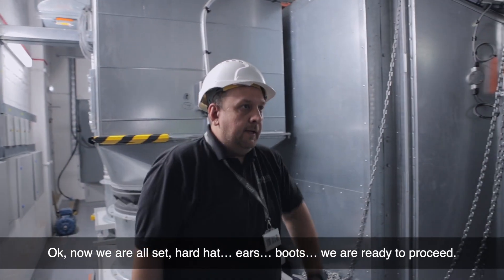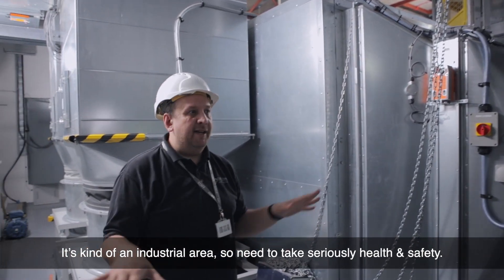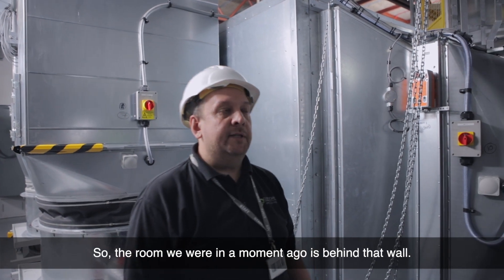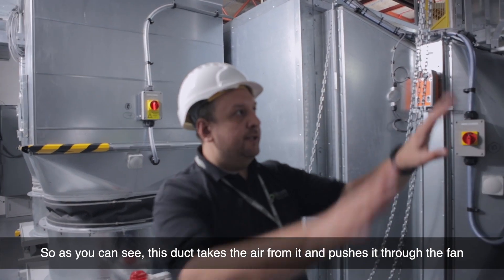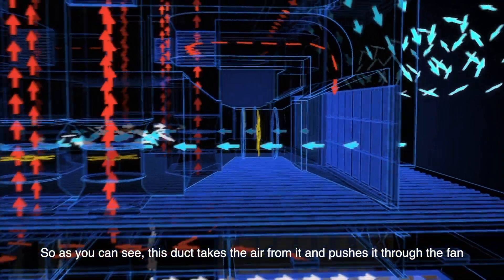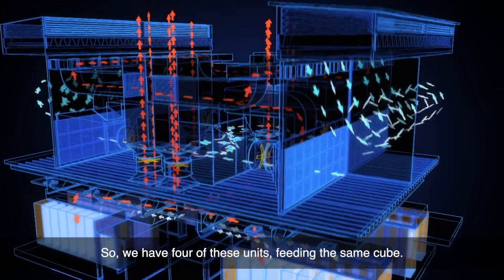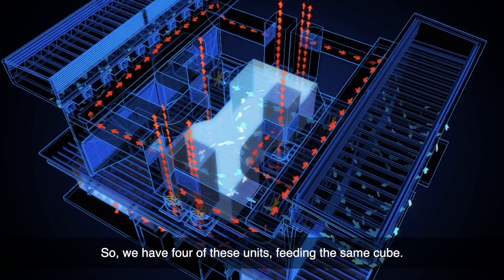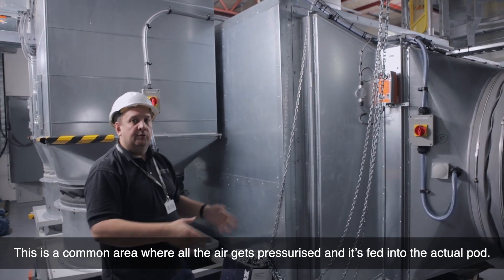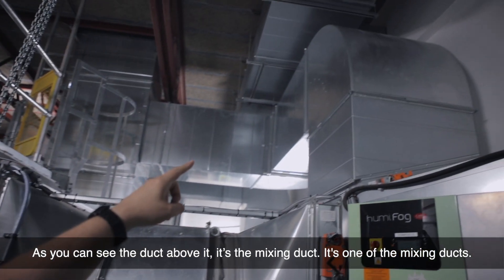Now we're all set — hard hat, ears, boots. We're ready to proceed because it's a kind of industrial area, so we need to take serious considerations. The room we were in a moment ago is behind that wall. This duct takes the air from it and pushes it through the fan into the pressure chamber, which we call the cube. We have four of those units feeding the same cube — it's a common area where all the air gets pressurized and is fed into the actual pods. The duct above it is the mixing duct.